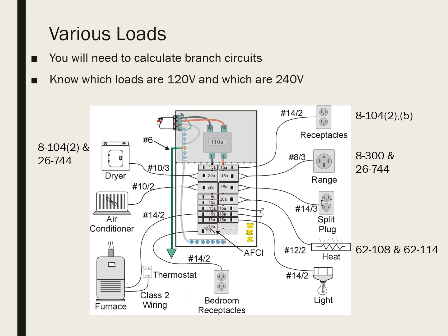Typical loads inside a house that do have 2-pole breakers are your range, your dryer, your air conditioner, and hot tubs if they have it. There may also be an electric water heater which may require a 2-pole breaker as well. So make sure you're double checking on all the different loads. After that, all you have to do is count how many circuits are required. Remember, 2 spots for any 2 poles, single slots for any single pole.